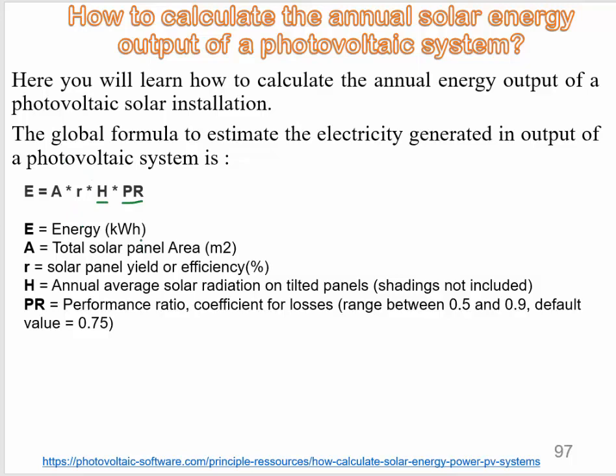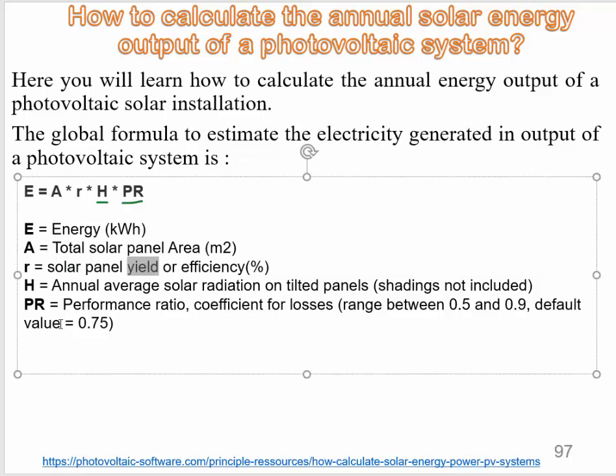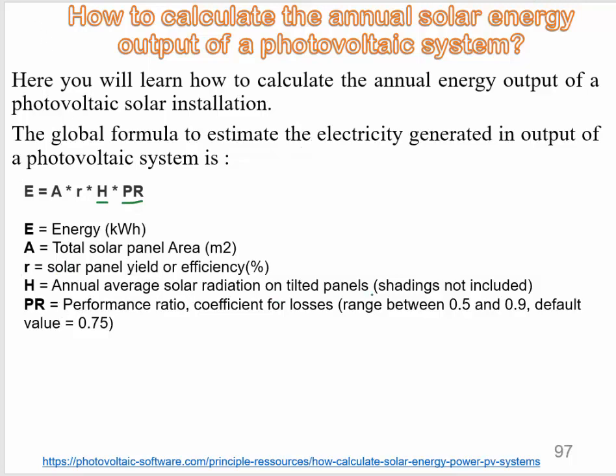E is the energy, measured in kilowatt-hour. A is the total solar panel area, measured in square meters. R is the solar panel yield or efficiency. H is the annual average solar radiation on tilted panels, shading not included — we suppose the panels are in direct sunlight. PR is the performance ratio coefficient for losses.